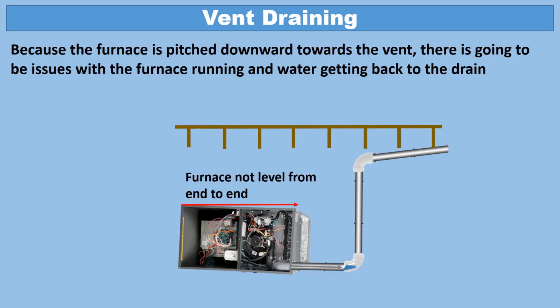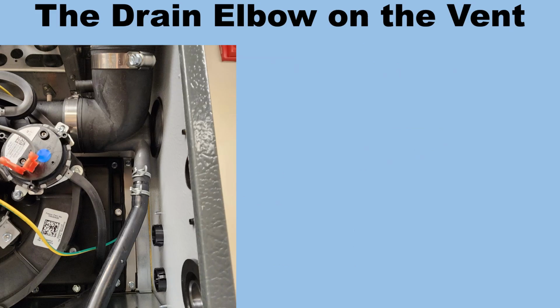Because the furnace is pitched downward towards the vent, there is going to be issues with the furnace running and water getting back to the drain. Again, you have to have that furnace level from end to end, or you will get water to build up right at the 90 as you see there. The drain elbow of the vent.